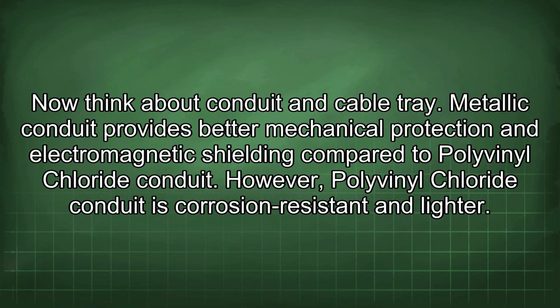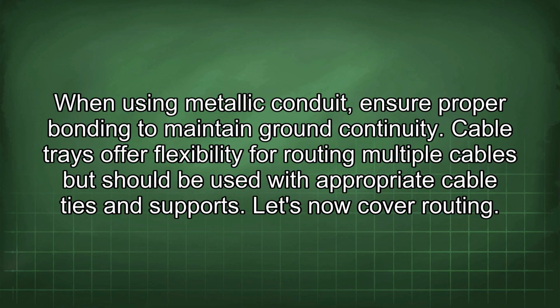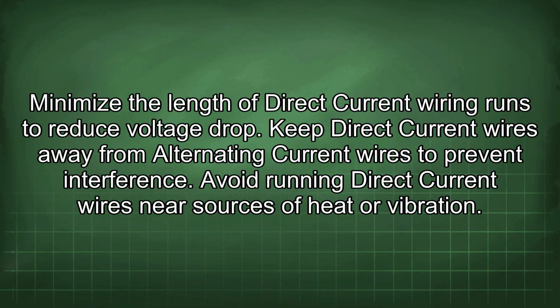Now think about conduit and cable tray. Metallic conduit provides better mechanical protection and electromagnetic shielding compared to polyvinyl chloride conduit. However, polyvinyl chloride conduit is corrosion resistant and lighter. When using metallic conduit, ensure proper bonding to maintain ground continuity. Cable trays offer flexibility for routing multiple cables but should be used with appropriate cable ties and supports. Let's now cover routing. Minimize the length of direct current wiring runs to reduce voltage drop. Keep direct current wires away from alternating current wires to prevent interference. Avoid running direct current wires near sources of heat or vibration.